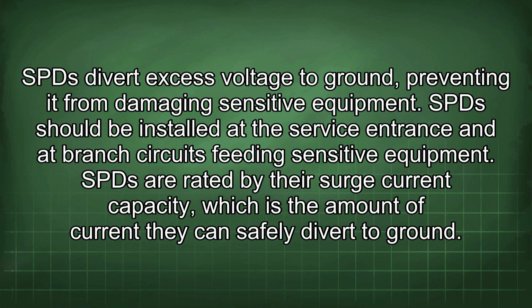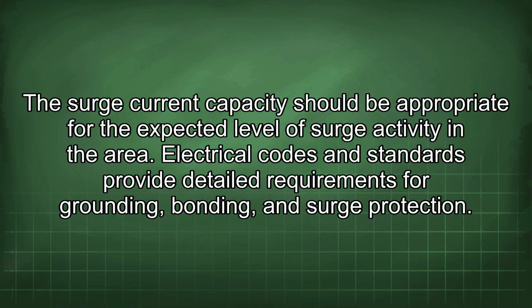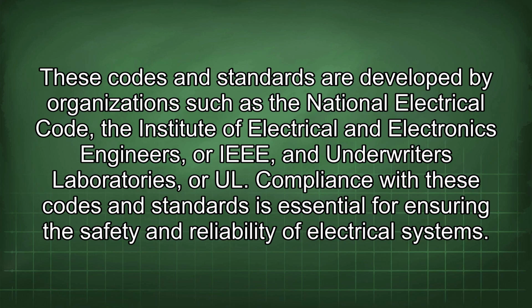SPDs are rated by their surge current capacity, which is the amount of current they can safely divert to ground. The surge current capacity should be appropriate for the expected level of surge activity in the area. Electrical codes and standards provide detailed requirements for grounding, bonding, and surge protection. These codes and standards are developed by organizations such as the National Electrical Code, the Institute of Electrical and Electronics Engineers, or IEEE, and Underwriters Laboratories, or UL.